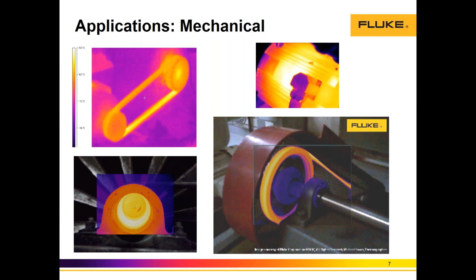Let's also talk about mechanical or electromechanical inspections, which cover a diverse variety of equipment. Most inspections in motors, rotating equipment, and steam traps are not quantitative inspections, they're qualitative. The light color areas on both thermal images on belts, pulleys, indicate we might have an alignment issue or a friction issue. There's an interesting image here also: you can notice on the top right motor, I think it's a pump, there's a concentrated pattern of heat in the center area, which indicates there might be some issues with the stator, possibly impacting the electrical insulation.